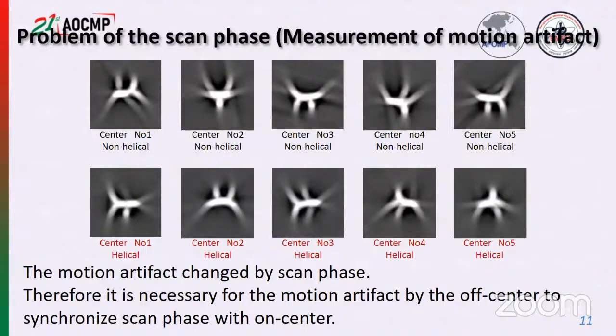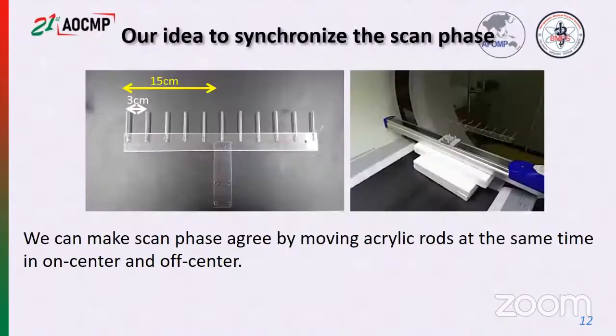Problem of the scan phase. The motion artifact changes with the scan phase. Therefore, to evaluate the motion artifact at off-center, it is necessary to synchronize the scan phase with on-center. Our idea to synchronize the scan phase: we can make the scan phase agree by moving acrylic rods at the same time in on-center and off-center.